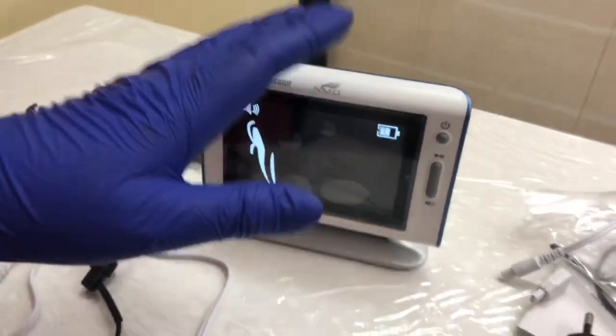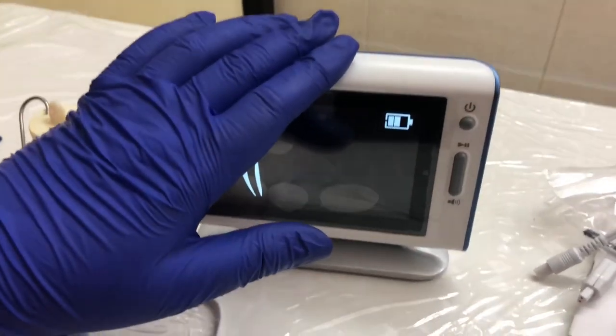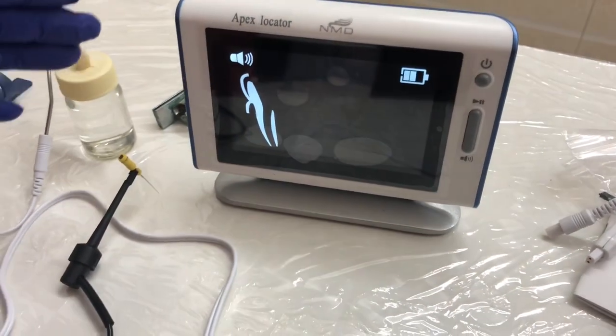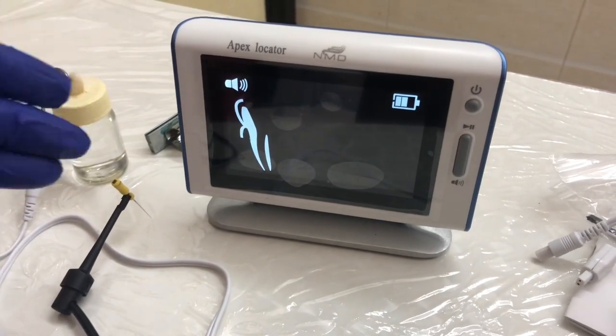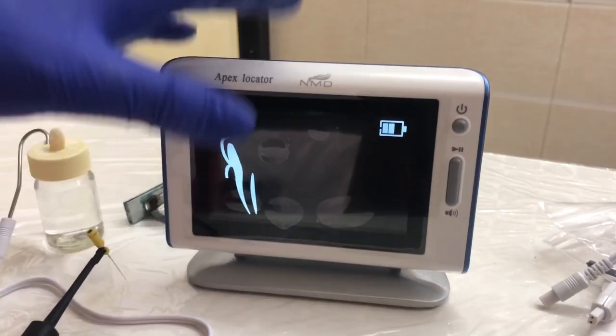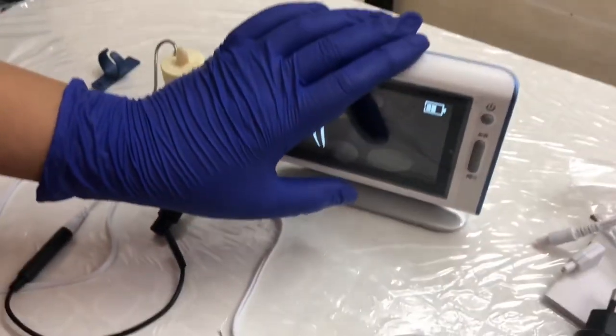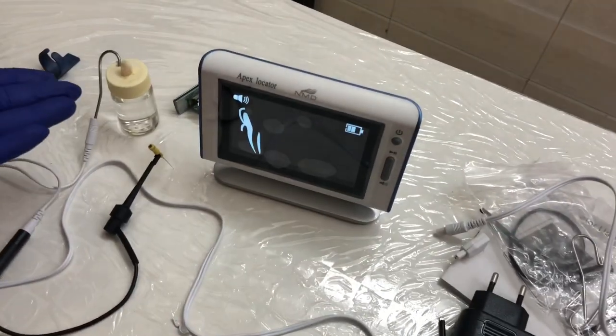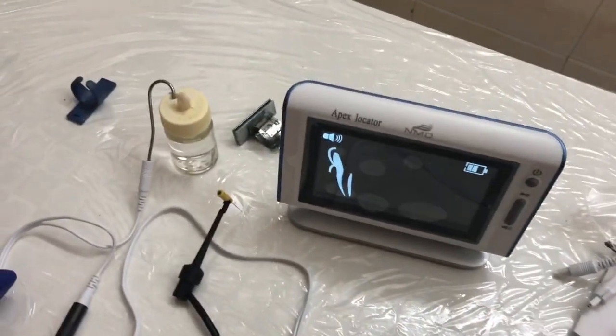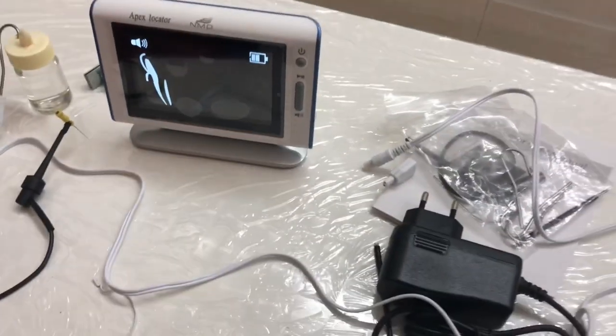Where you cannot use this apex locator: basically where there is a big perforation or if blood spilling is present, you can re-measure once the bleeding is stopped. Also avoid use with gum hyperplasia, cracked teeth, calcified canals, or if the roots are extremely dry — in that case, put some saline inside and then use it.